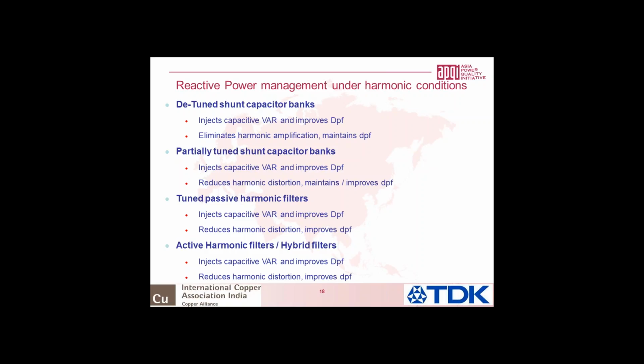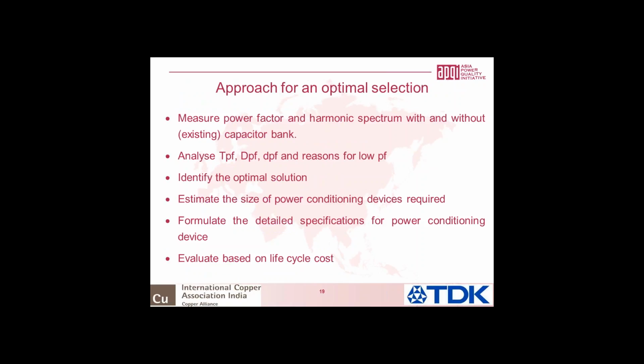Now, the approach to do this would be, in my opinion, we need to measure power factor and harmonic spectrum with and without the existing capacitor bank. This would be the first key if anybody wants to do reactive power compensation in a harmonic-rich environment. We need to measure the power factor and the harmonic spectrum with and without the existing capacitor bank, which will give away any clues as to whether you're having any harmonic amplification. Then we need to analyze the harmonic spectrum, true power factor, displacement and distortion power factor, and identify reasons for low power factor. And as I said, identify optimal solutions.